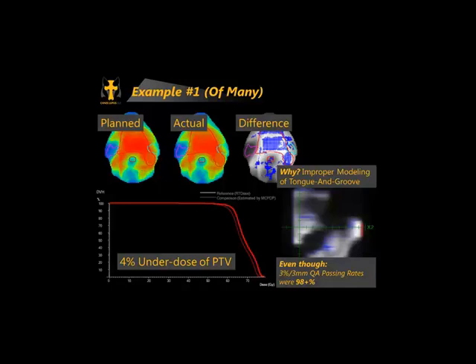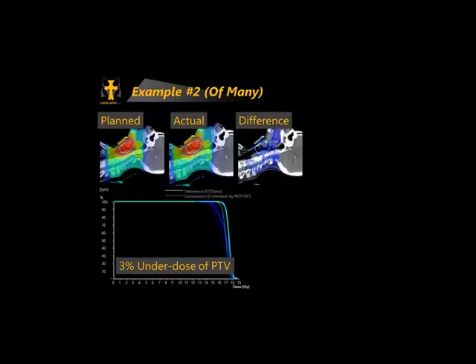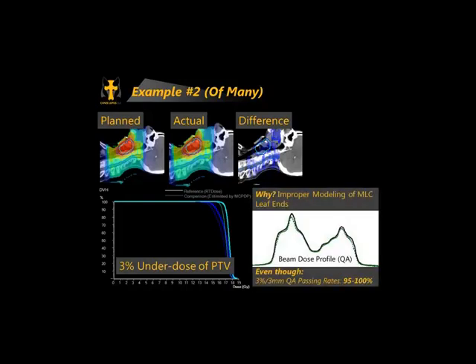This case had almost perfect QA passing rates, but the tongue-and-groove effect — visible as blue stripes — was really happening and sucking dose out. It wasn't being deposited in the patient the way the treatment planner thought. This was a physics problem, not a treatment planning problem, but it was causing a shift in the dose actually being delivered. One very simple thing in the planning system affects treatment planning.